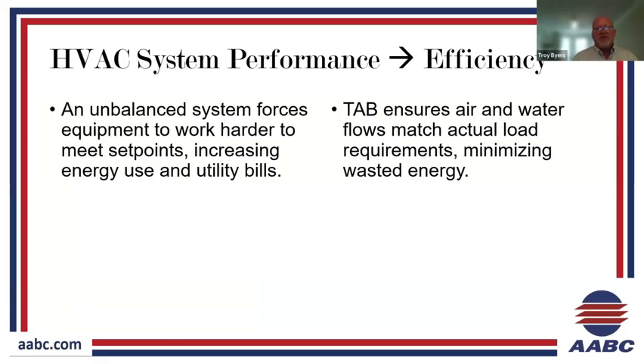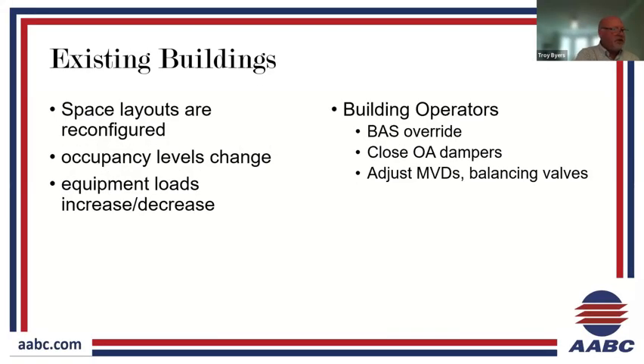So clearly, an unbalanced system is going to force equipment to work harder to meet set points, and that's going to increase our energy use. And so our TAB is going to ensure that our air and water flows match the actual load requirements, again, considering these loads may have changed from the original design. Some examples of that would be space layouts. So literally moving walls, or demoing walls, or adding walls, changing space layouts. And the HVAC system needs to be reviewed. The HVAC distribution of airflow needs to be reviewed at that point, and changes need to be made accordingly.